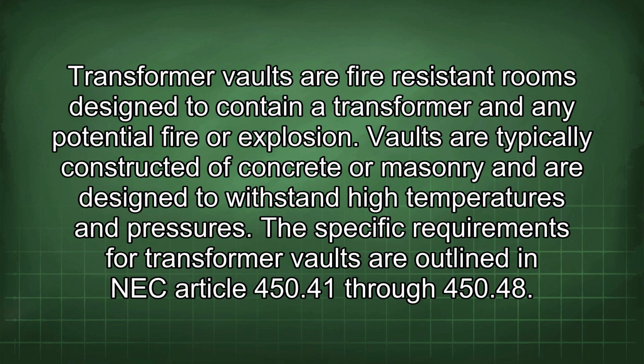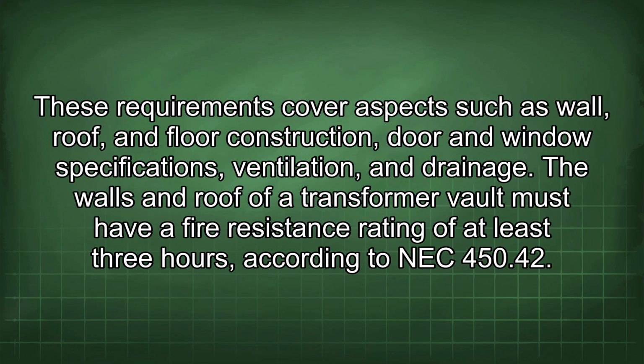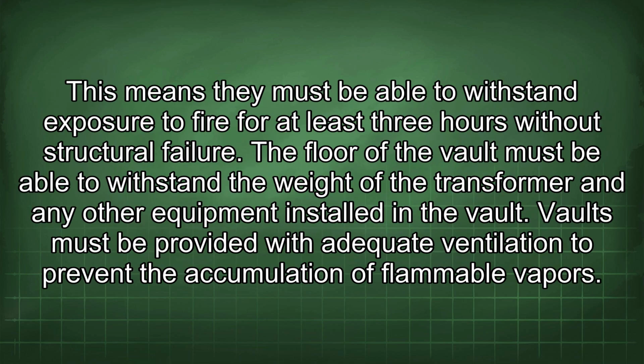Vaults are typically constructed of concrete or masonry and are designed to withstand high temperatures and pressures. The specific requirements for transformer vaults are outlined in NEC Article 450.41 through 450.48. These requirements cover aspects such as wall, roof, and floor construction, door and window specifications, ventilation, and drainage. The walls and roof of a transformer vault must have a fire resistance rating of at least 3 hours according to NEC 450.42.